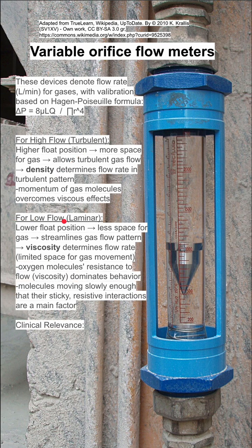For low flow situations, the flow tends to be more laminar. You have a lower float or bobbin position, which means there is less space for the gas to come around. This streamlines the gas flow pattern, and in this case the flow rate is determined mainly by the gas's viscosity.